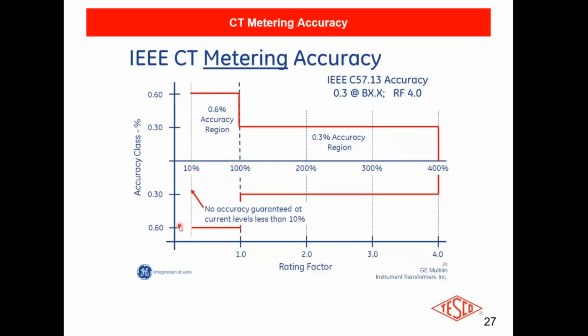So you're effectively getting no meaningful billing data, which means if I put a 400 to 5, 10% of that is 40 amps. Well, if I've got a customer only drawing 200 to 300 amps typically, at night with just the lights on and a few computers and stuff, he may only be drawing 10 or 20 amps. So basically I'm giving away all the power in the evenings.